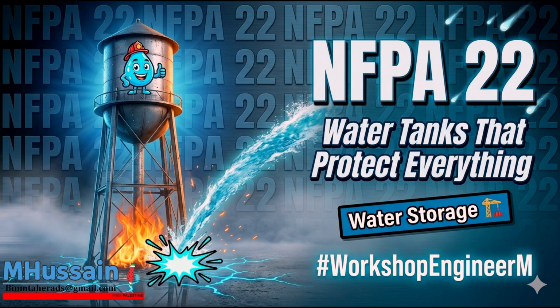Accessibility equals maintainability. If a critical component is dangerous or exceedingly difficult to reach, human nature dictates it simply won't get maintained. The NFPA writes maintenance accessibility directly into the design constraints. Which is how you guarantee the system will actually work when it's called upon decades later.